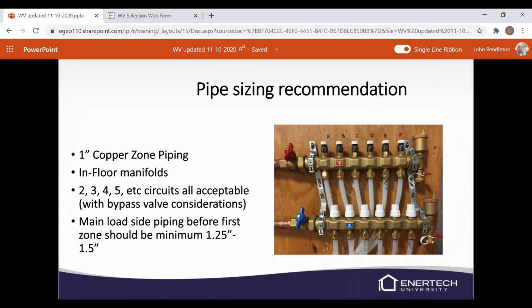Pipe sizing, 1-inch copper piping. You can use these in-floor manifolds in the picture here. Make sure when you're installing manifolds that they're in this horizontal position. Do not install these in the vertical position. If you do that, they're not going to vent air properly, and you could have problems with water flow. So make sure that they're in the horizontal position like they are here in this picture.